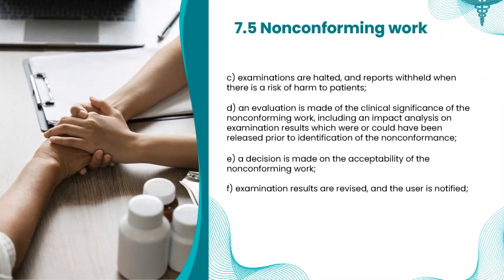Examinations are halted and reports withheld whenever there is a risk of harm to patients. An evaluation of the clinical significance of the non-conforming work is conducted, including an impact analysis on examination results that were, or could have been, released prior to the identification of the non-conformance. A decision on the acceptability of the non-conforming work is made and documented.